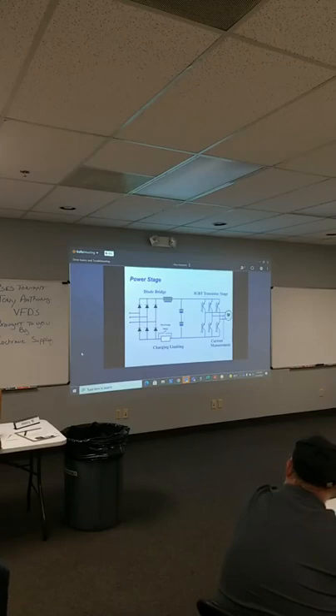If you're not seeing that, one thing you may want to do is check your diode bridge. And it's very easy. You can actually check it with an ohm meter. Obviously make sure power's off the drive and disconnect the line leads coming in. If you know anything about diodes, they're nothing more than a fancy switch. They are either on or off. They allow current flow in one direction and block it in the other.